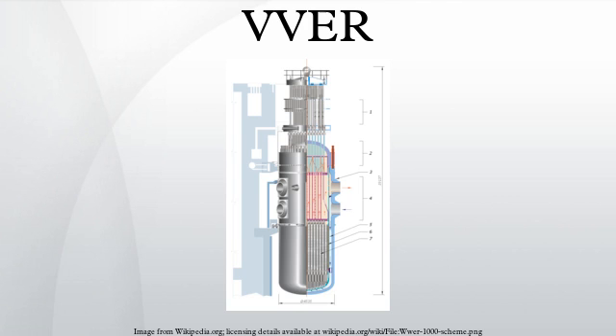The secondary circuit also consists of different subsystems. Secondary water is boiled in the steam generator, taking heat from the primary circuit. Before entering the turbine, remaining water is separated from the steam so that the steam is dry. The expanding steam drives a turbine connected to an electrical generator; the turbine is split into high and low pressure sections, and steam is reheated between these sections to prevent condensation. Reactors of the VVER-1000 type deliver 1 GW of electrical power. The condenser cools and condenses the steam, shedding waste heat into a cooling circuit. A deaerator removes gases from the coolant, and circulation pumps are each driven by their own small steam turbine. Steam from the turbine is taken to reheat coolant before the deaerator and steam generator. Water in this circuit is not supposed to be radioactive.